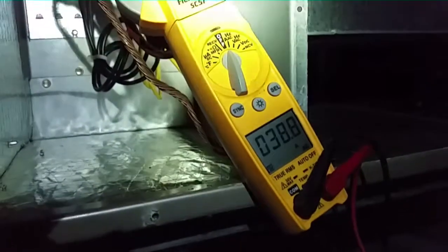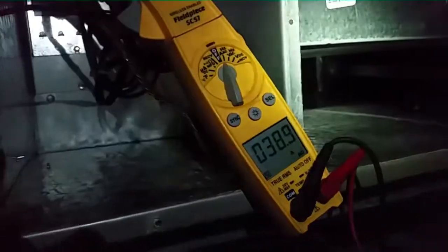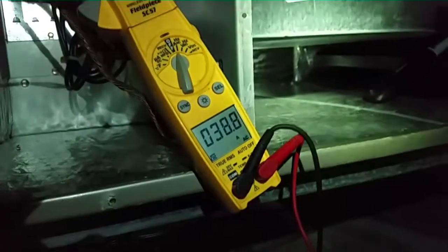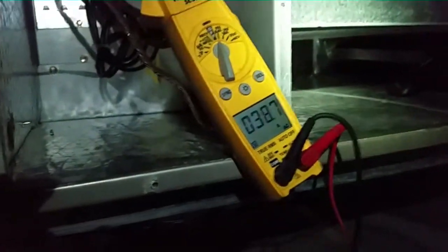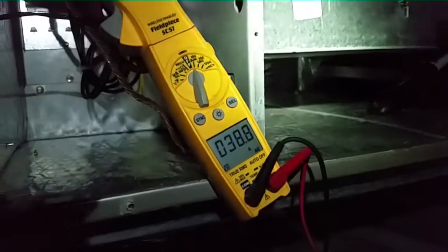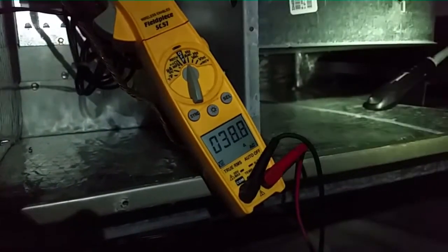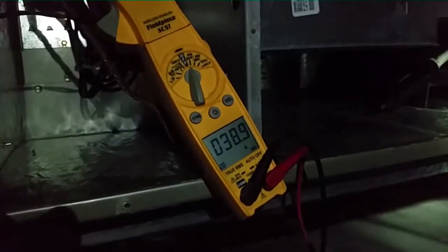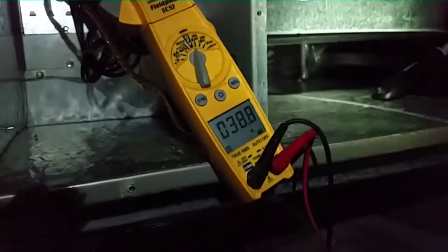We have all heat strips on. In fact, you can see them. Turn this off. You can see the light from the heat strips in there if you look real close. Kind of hard to see, but you can see faintly up there. So we're going to close the door and do a little CFM test, and then we'll head outside to check the charge, or just monitor the charge more in heating. In cooling, I do a more comprehensive check, and in heating, I just want to make sure it's close to where it should be.